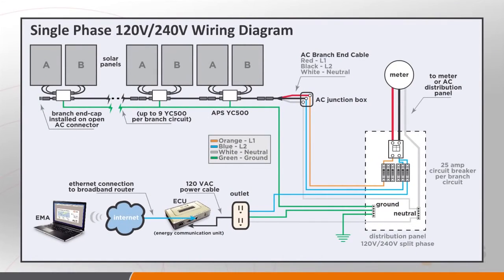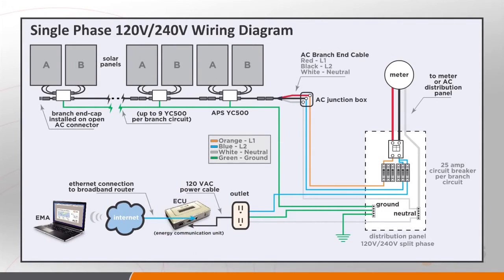This is a simplified typical residential single-phase system diagram. The YC500 is assigned to two PV modules, typically described as side A and side B. When hooking up the AC cabling, there are three conductors: the red L1, the black L2, and then the neutral, which is used in the PLC communication with the ECU. A quick word on ECU placement: the ECU is plugged into a standard 120-volt outlet, and you want to get it installed as close electrically as possible to the array to eliminate as many communication problems as possible.